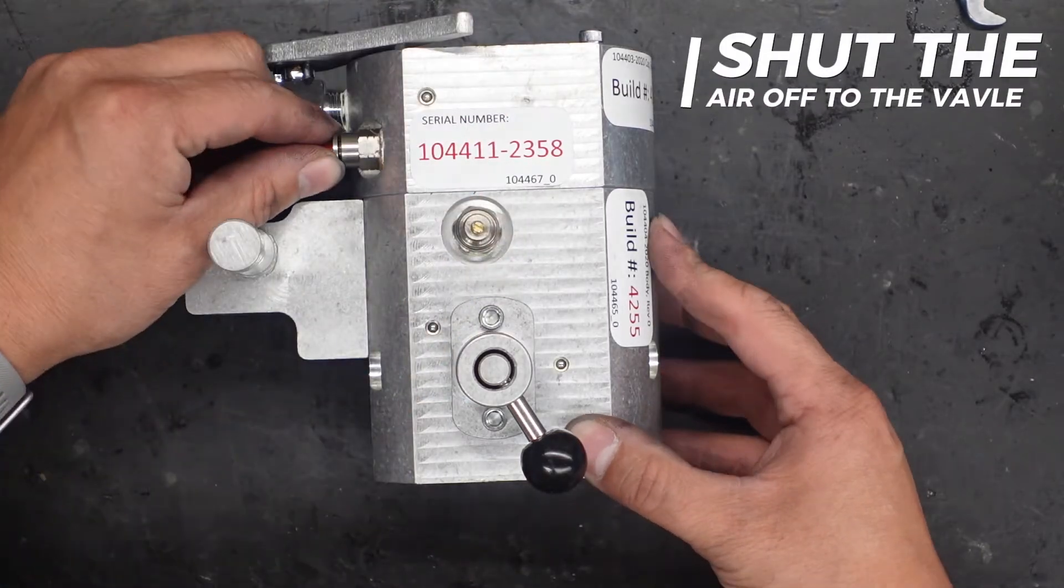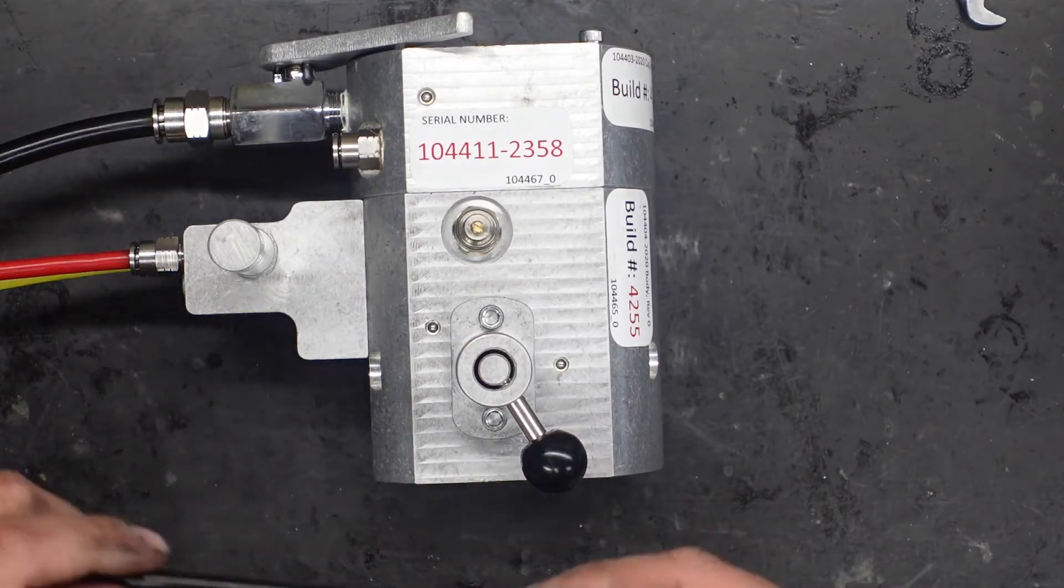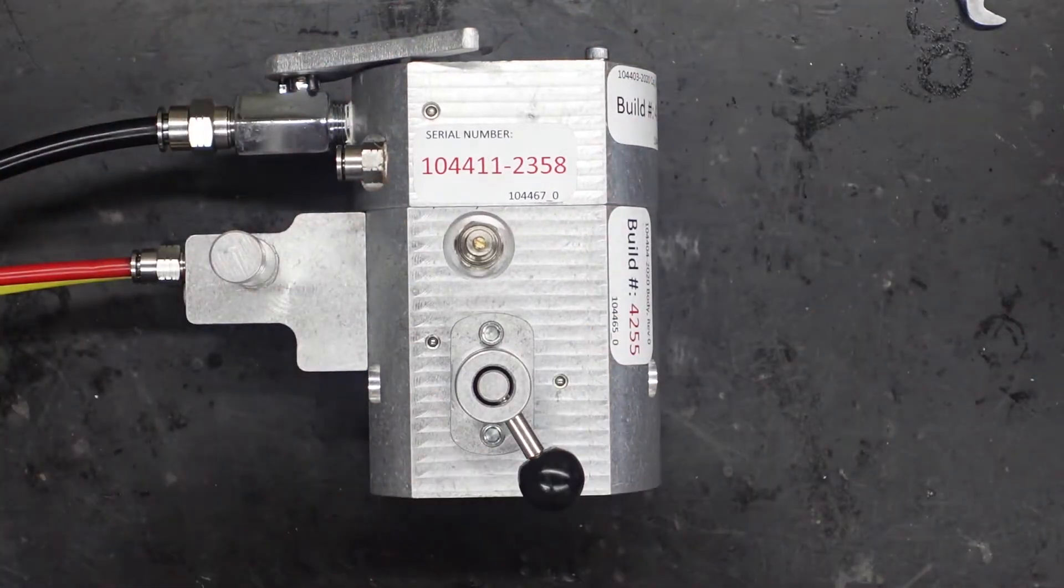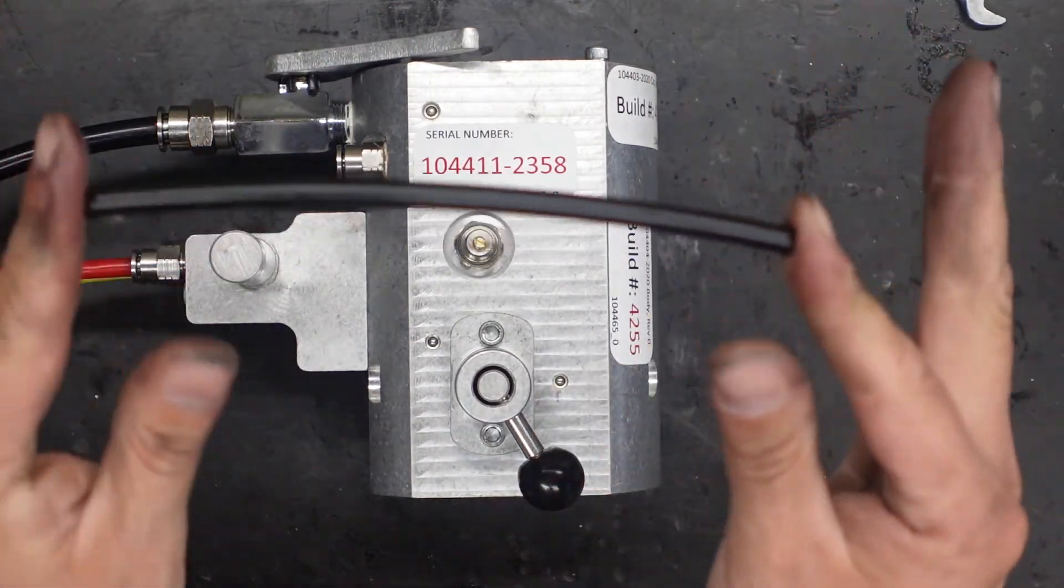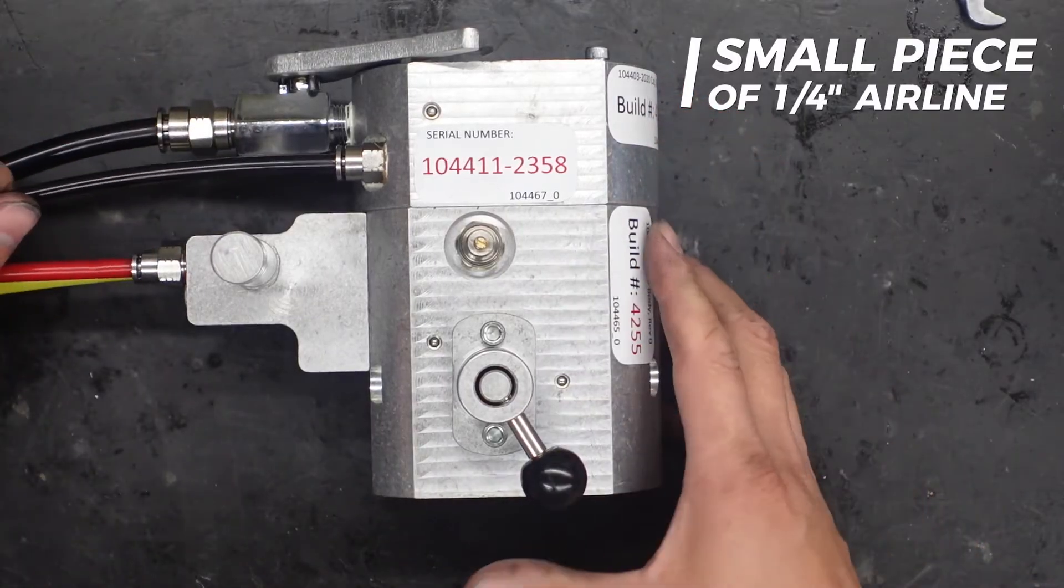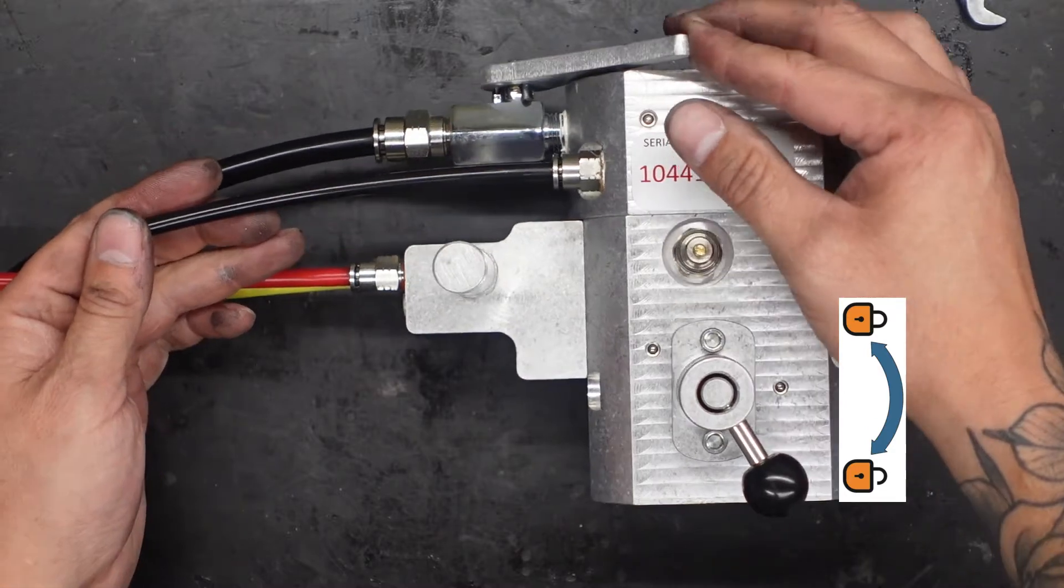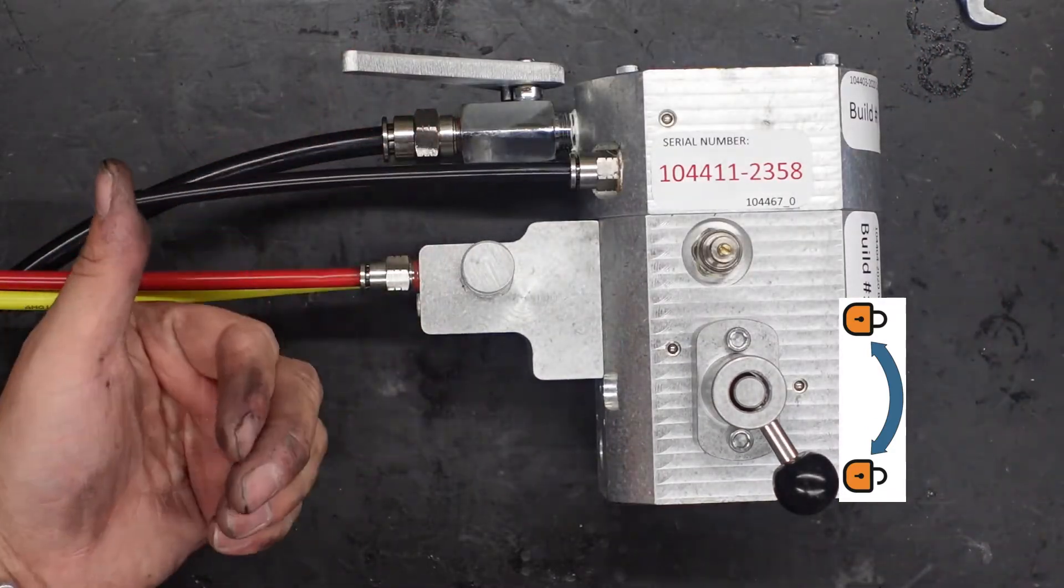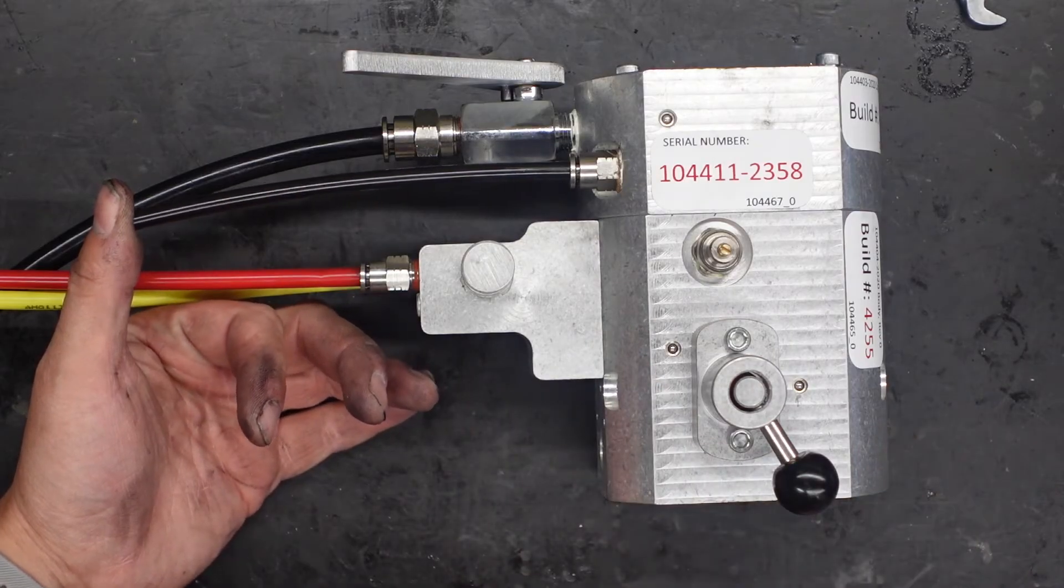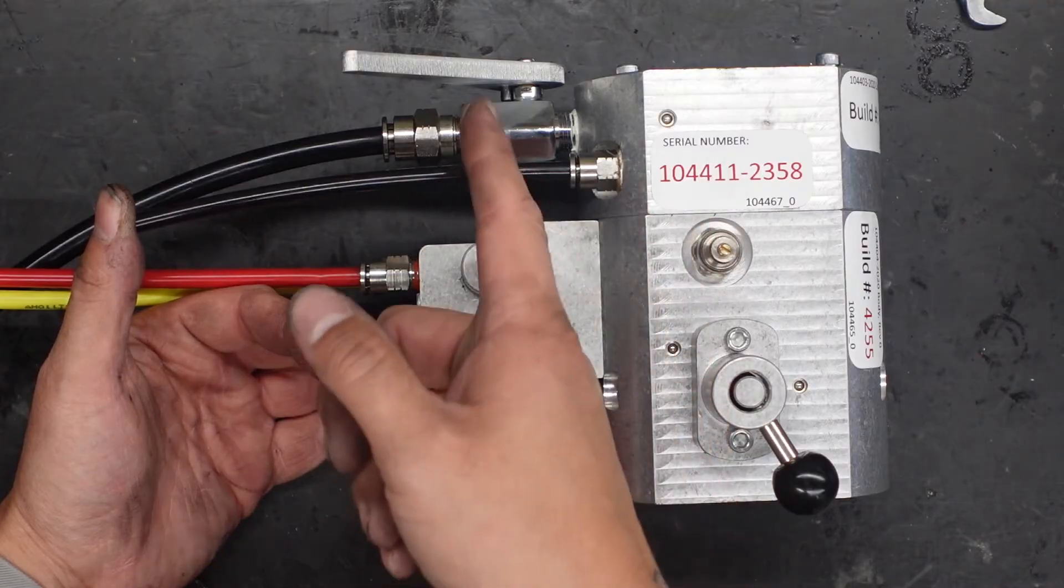I take a small chunk of airline to get at least outside the box. I'm luckily have this one out of the box already. So you're going to take a small chunk of quarter-inch airline, connect it into that seal, and go ahead and put your air back to the valve. You hear it's running. If you cap it with your thumb that cycling should stop.